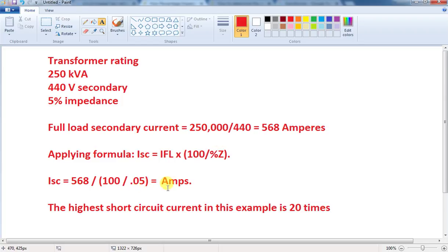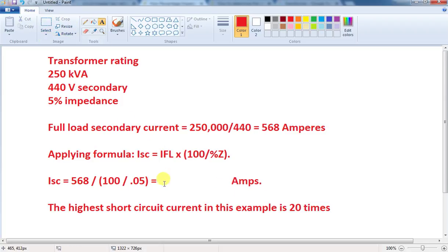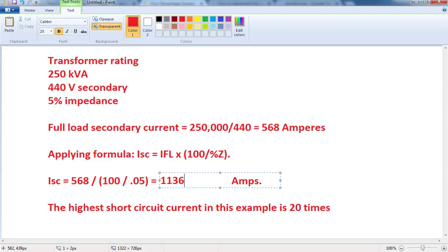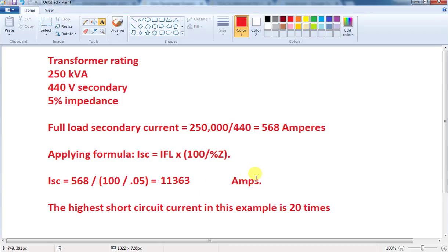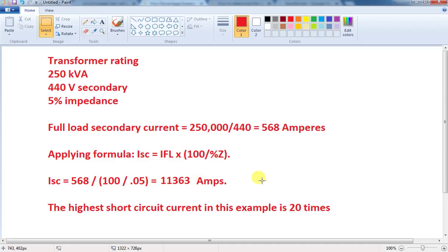So, applying that formula, the result is 11,363A. That is approximately 11kA. This is the maximum short circuit current that the transformer can produce under short circuit conditions. That is a key figure.